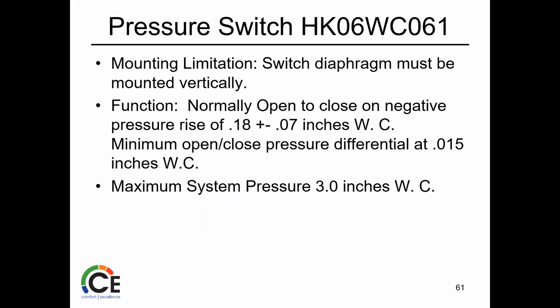So pressure switch, if the unit has it, depending on what it's there, just a basic diaphragm switch, nothing out of the ordinary there. Normally open to close on negative pressure. Just like the furnaces do, the residential furnaces, same basic way. Just anything more than 3 inches of water column is going to destroy the diaphragm. So just be careful if you're trying to blow in at the test, you might blow the diaphragm.